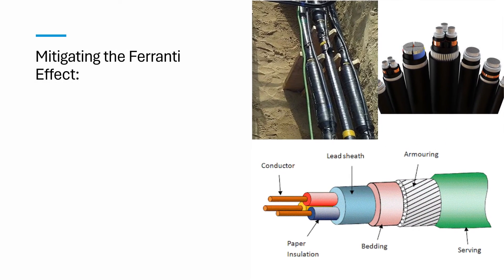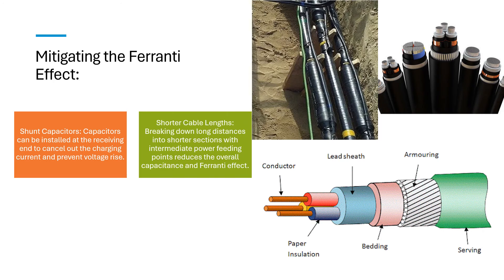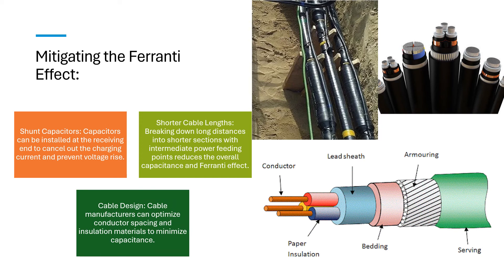Mitigating the Ferranti effect. Shunt capacitors can be installed at the receiving end to cancel out the charging current and prevent voltage rise. Shorter cable lengths: breaking down long distances into shorter sections with intermediate power feeding points reduces the overall capacitance and Ferranti effect. Cable design: cable manufacturers can optimize conductor spacing and insulation materials to minimize capacitance.